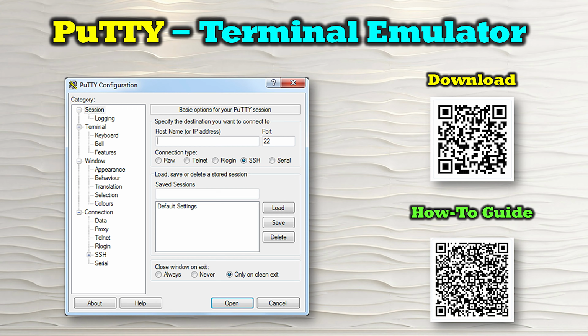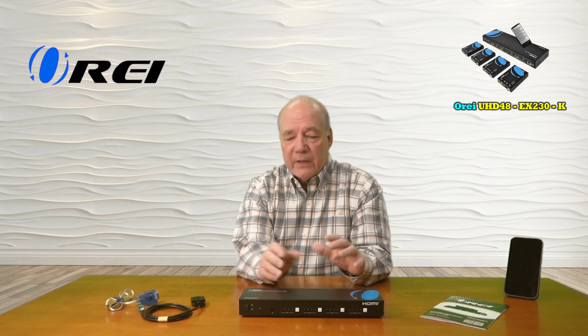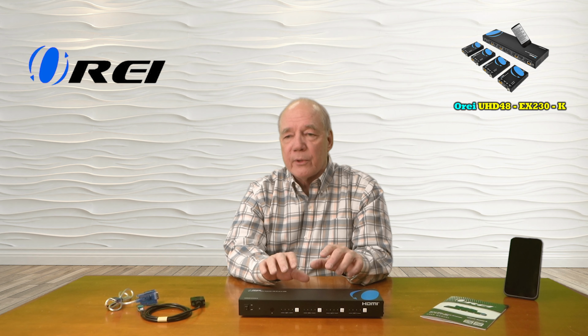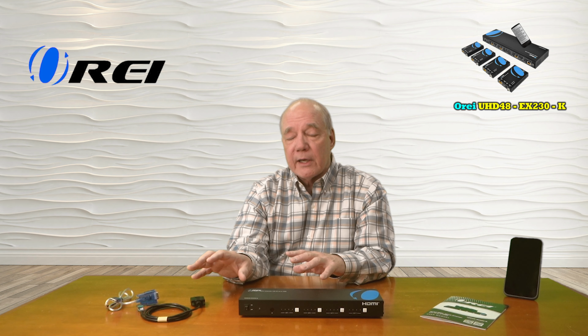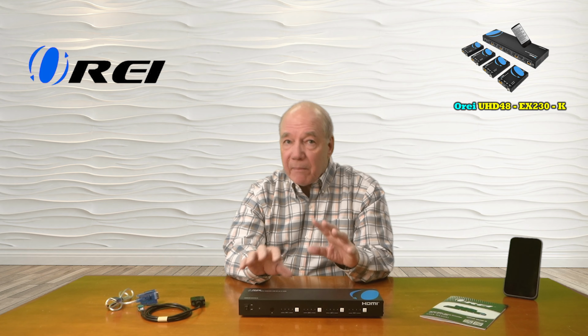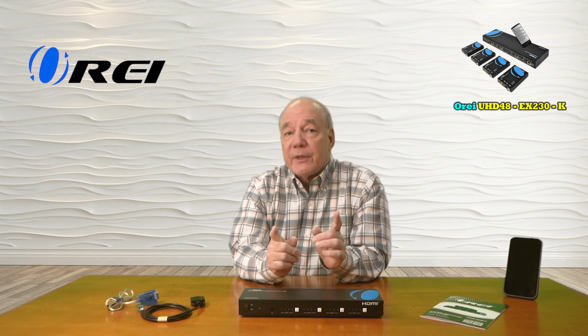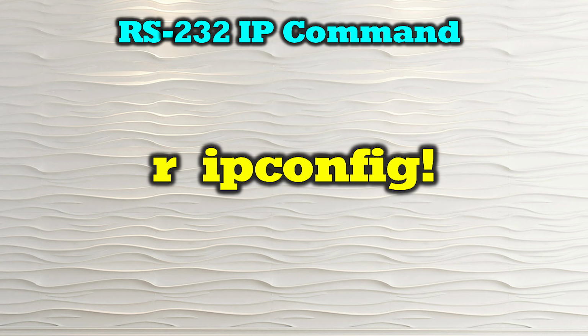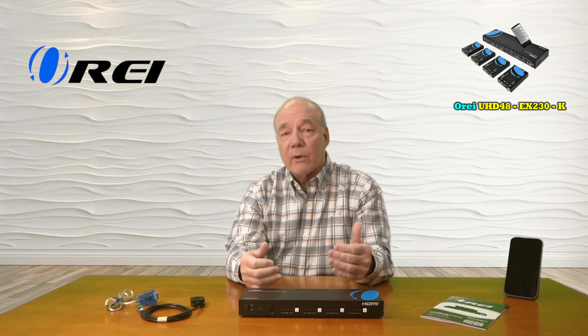Now I have a QR code on the screen where you can download PuTTY for free, and that's a terminal emulator that allows you to issue commands on your computer over that RS-232 connection to control the unit. Now you can issue a wide variety of commands to actually make changes to the configuration, but the command you'll want to issue to figure out the current IP address, if you haven't found it another way, is lowercase r ipconfig exclamation point. And that'll return the current IP address, the gateway, and the network mask.